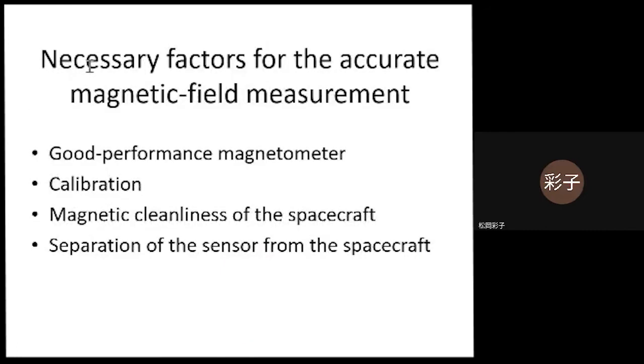There are some necessary factors for accurate magnetic field measurement. The first is, of course, good performance - we need a good performance magnetometer for very accurate magnetic field measurement. The second is we make calibration to obtain the parameters to calibrate the data and convert it into physical values.